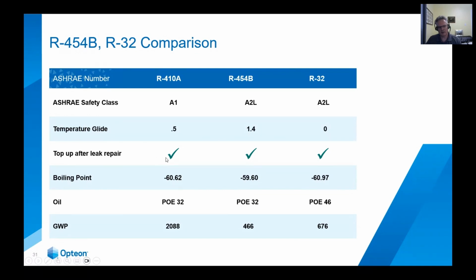It says top up after leak. This means that if I have a 454B system or a 32 system and it were to leak that refrigerant, I can then top it back up with that same refrigerant. You should never mix refrigerants. You should never put 32 in a 454B system or vice versa. And you should never put 454B or 32 in a 410A. So you cannot top up a 410A system with either of these refrigerants. You cannot do that. You should always stick to what refrigerant is in the system.